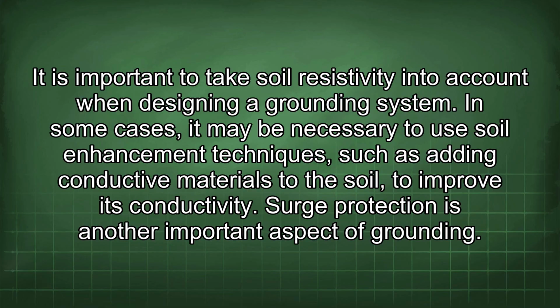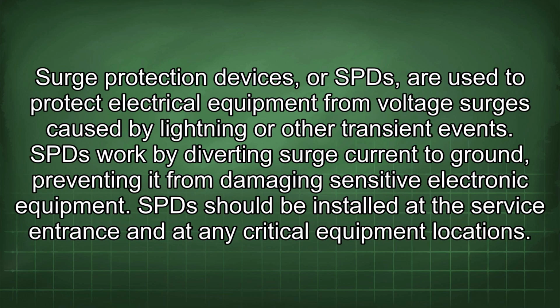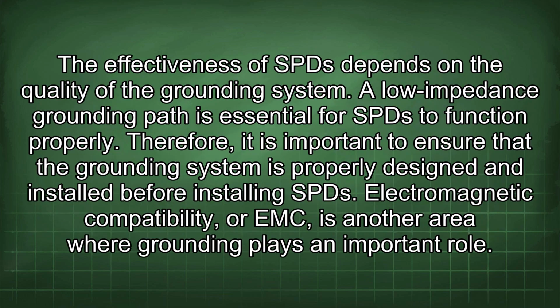to improve its conductivity. Surge protection is another important aspect of grounding. Surge protection devices, or SPDs, are used to protect electrical equipment from voltage surges caused by lightning or other transient events. SPDs work by diverting surge current to ground, preventing it from damaging sensitive electronic equipment. SPDs should be installed at the service entrance and at any critical equipment locations. The effectiveness of SPDs depends on the quality of the grounding system. A low impedance grounding path is essential for SPDs to function properly. Therefore, it is important to ensure that the grounding system is properly designed and installed before installing SPDs.